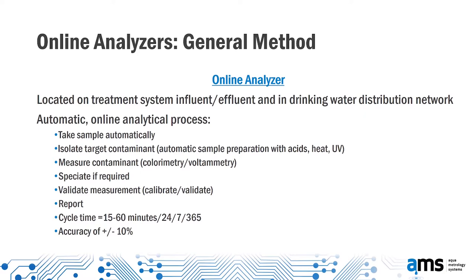We need to get all of the selenium in that sample, not half of it — it's no good accurately measuring half the selenium. So that involves a lot of sample preparation with acids, heat, and ultraviolet light to extract the contaminant of concern. We then move on to measurement itself, where we employ two principal technologies: colorimetry and voltammetry, with the method chosen according to the contaminant of concern.